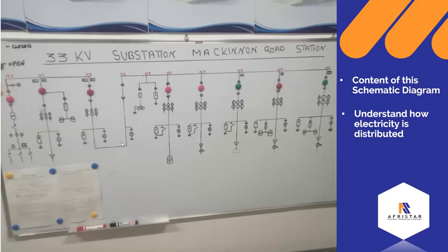Because of safety measures, we have 3 power sources in our substation. We have Kenya Power side on N2, and on N9 we have power from Voi station, and on N10 we have power from Mombasa West substation.